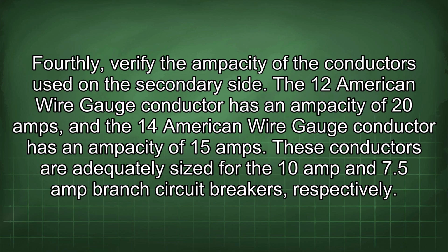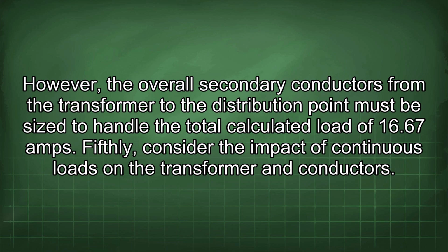Fourthly, verify the ampacity of the conductors used on the secondary side. The 12 American wire gauge conductor has an ampacity of 20 amps, and the 14 American wire gauge conductor has an ampacity of 15 amps. These conductors are adequately sized for the 10 amp and 7.5 amp branch circuit breakers respectively. However, the overall secondary conductors from the transformer to the distribution point must be sized to handle the total calculated load of 16.67 amps. Fifthly, consider the impact of continuous loads on the transformer and conductors.